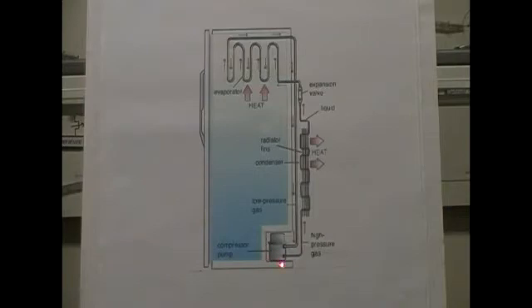Let's look at the compressor. This is your outlet. That's high pressure gas going into your condenser coil. And it releases heat to the surrounding. And the freon continues to go up to your expansion valve. Or some of you might have the capillary tube. And it's going to go into your evaporator. And it picks up heat from here and moves it out.